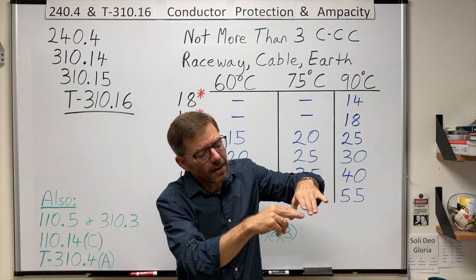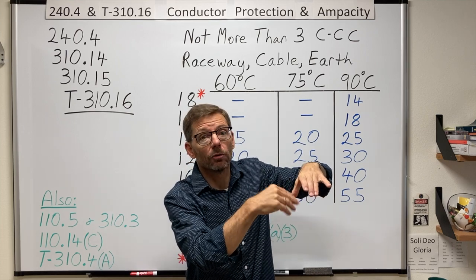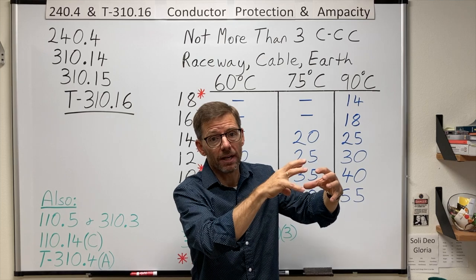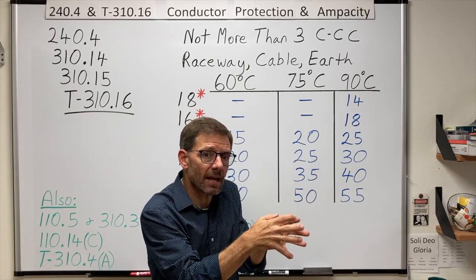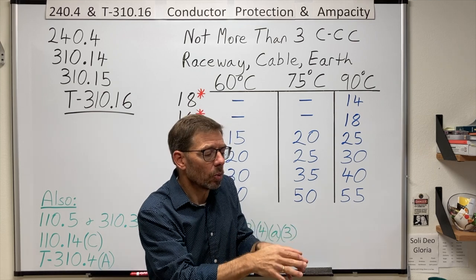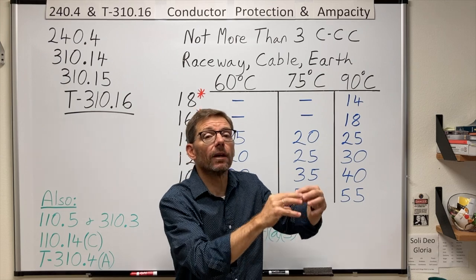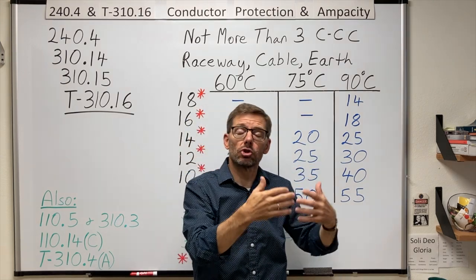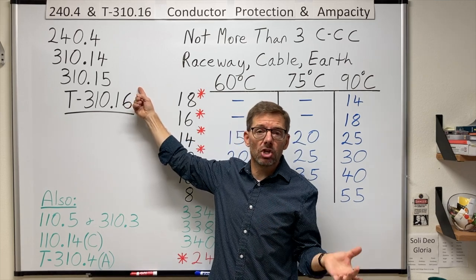So instead of having all those conductors at their top ampacity, and then they're kind of mutually heating each other up past their insulation ratings, we take all those conductors and restrict their ampacities. And so when they run at their new limits, sure, they heat each other up, but they don't get over their temperature ratings. In the NEC, that's referred to as ampacity adjustment.